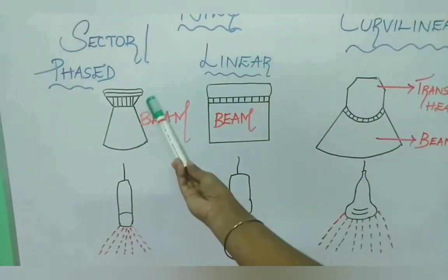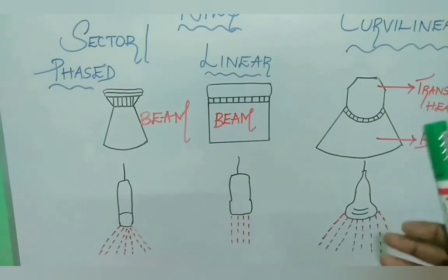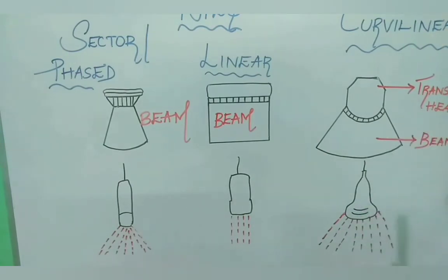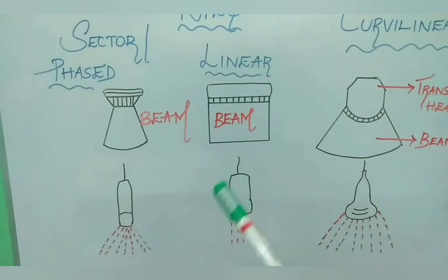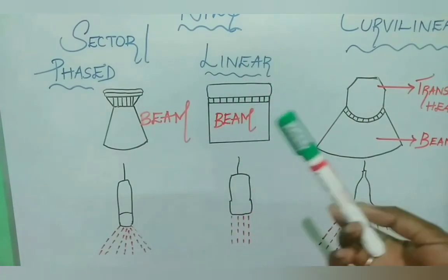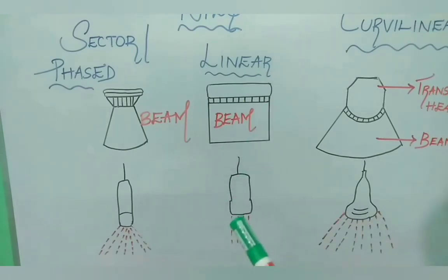Next is sector or phased array transducer probe. Phase refers to timing. Array refers to multiple elements. Here the beam is controllable because each element in this phased or sector array transducer probe can be pulsed individually at a computer calculated timing, in a programmed pattern. This type is mostly useful for cardiac imaging.